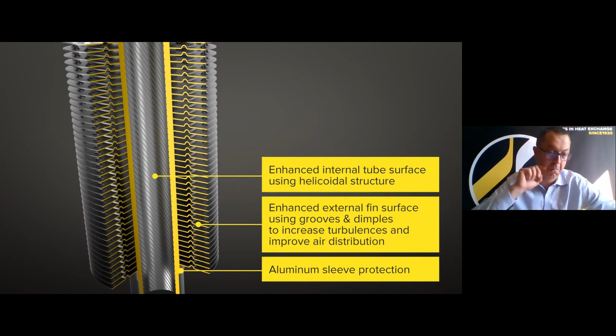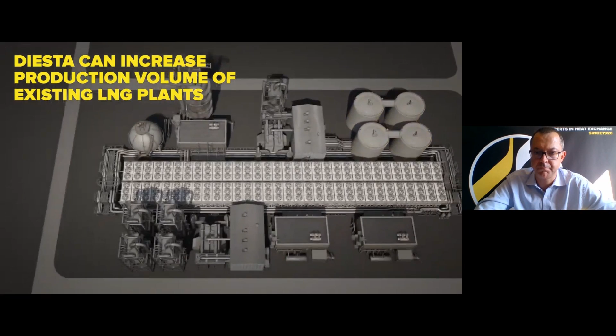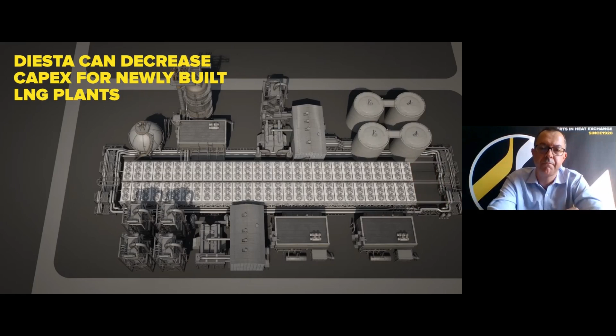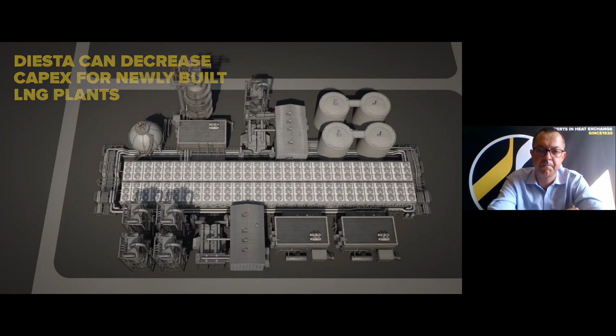By replacing regular tube bundles with DIESTA tubes in existing LNG trains, a colder outlet temperature of the refrigerant gas condenser can be achieved. This will increase LNG production volume while decreasing energy consumption and greenhouse gases per produced ton. Together, these benefits will more than offset the investment in DIESTA bundles within just a few months. Using DIESTA in newly erected natural gas liquefaction facilities leads to reduced capital expenses, resulting from a smaller plant footprint and lower overall construction and procurement costs.